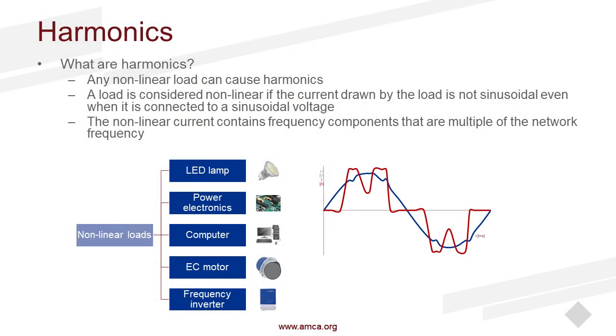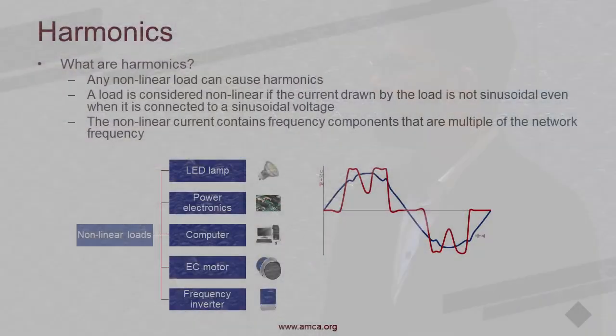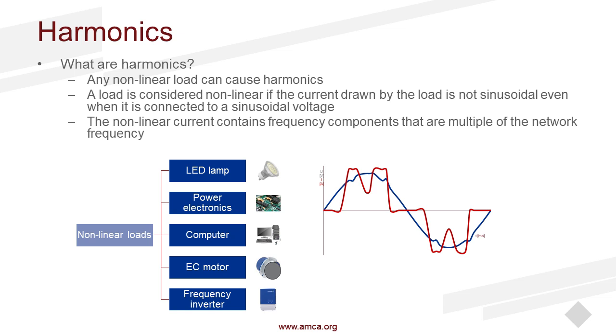What are harmonics? Where do they come from? So harmonics are caused from nonlinear loads. So these are loads that are taking a sinusoidal wave and converting it, manipulating it. This is coming from LED lamps, power electronics like we just discussed in the beginning, computers, EC motors, frequency inverters. And so you can see the red graph is showing your current, and with that distortion, now we're seeing that your blue curve, which is your voltage, is now becoming distorted. So these nonlinear loads are what is causing the harmonics. This is where it's coming from, when you're manipulating your voltage, your sinusoidal wave.